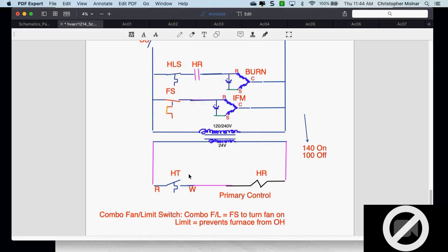Now, if my high limit opens on this wiring, do I lose my power to my thermostat? No. No. However, when these used to come wired from the factory, these were not put into place right here. Okay, they were put into... As I told you guys yesterday, there's about 6 different ways to wire these things. They were actually put into the wiring diagram down here.